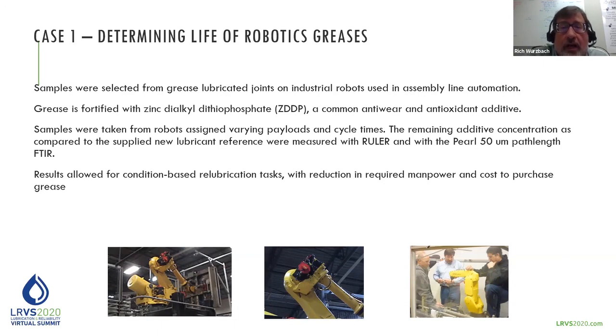The first one I kind of mentioned in the study that we did with the automotive manufacturer. I talked about the nearly $1,000 per year saving per robot. And this is how it was done: taking samples from these robot gears, 6 different locations on the robot, and overall a significant reduction in the cost of operating that asset, without even taking into account that we now have data about possible damage or the reliability of that component.